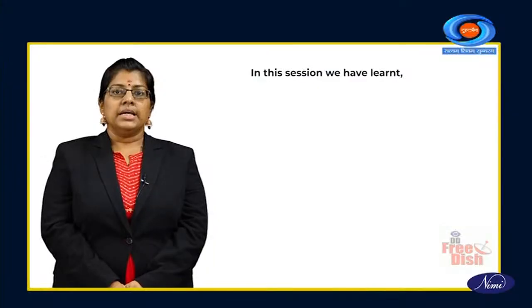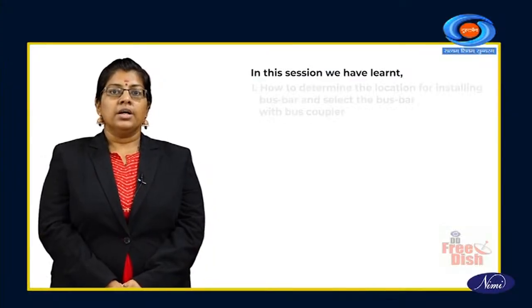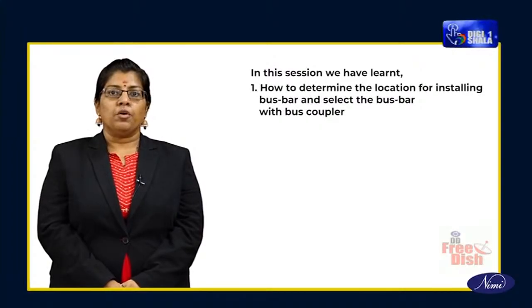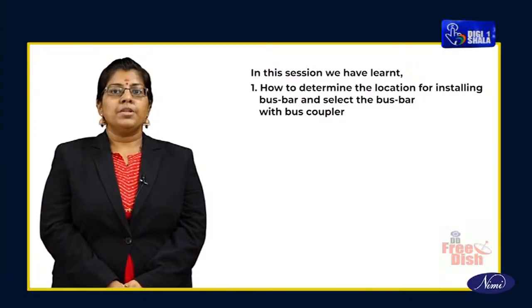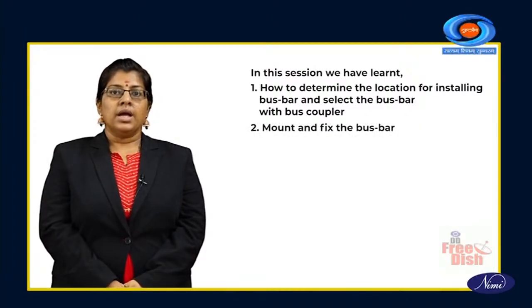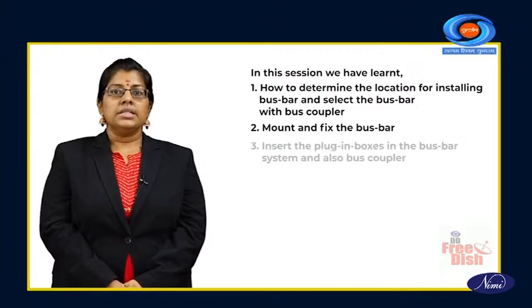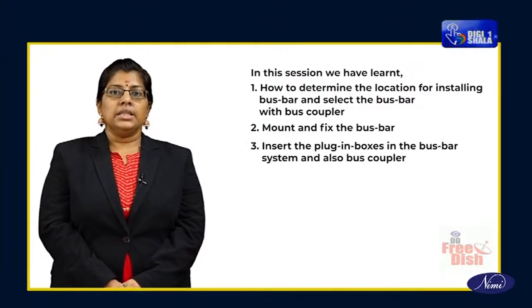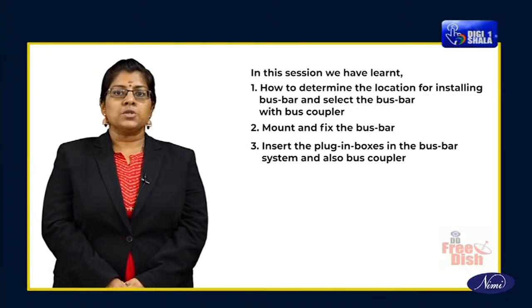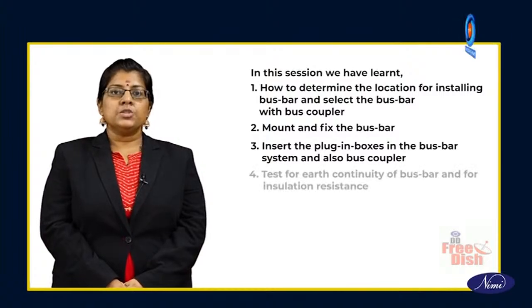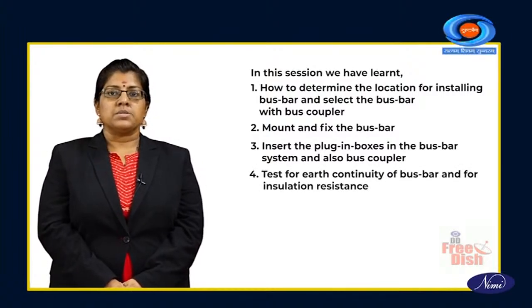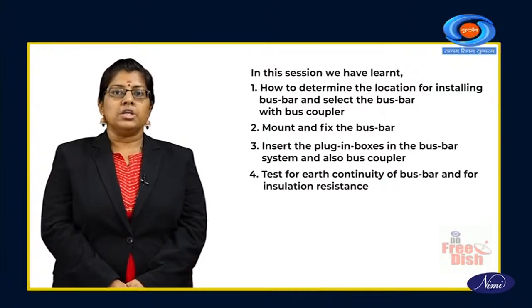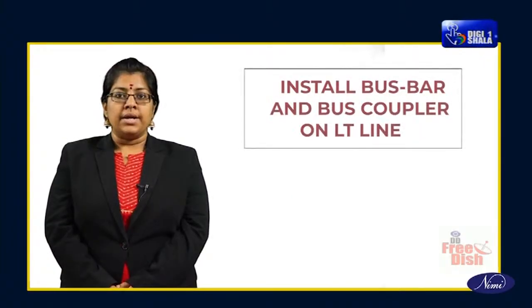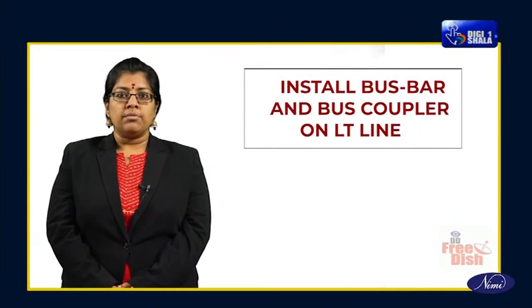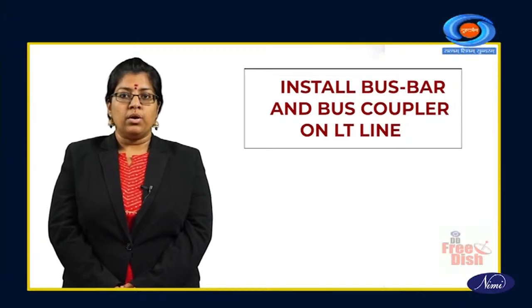Recap. In this session, we have learnt how to determine the location for installing the bus bar and select the bus bar with bus coupler, mount and fix the bus bar, insert the plug-in boxes in the bus bar system and also the bus coupler, and test for earth continuity of the bus bar and for insulation resistance. We must carry out these processes with utmost care and safety precautions.